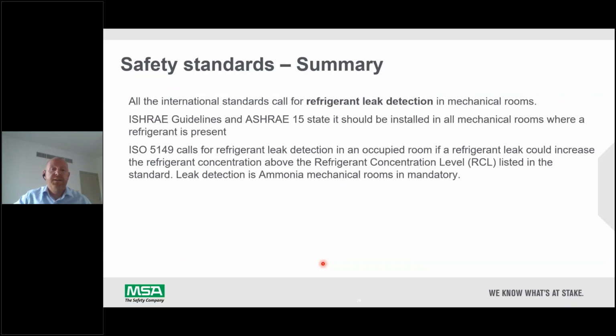So, safety standards, a summary. All of the international standards actually call for leak detection in the mechanical rooms at least. ISHRAE and ASHRAE say it needs to be installed in the mechanical rooms where refrigerant is present. And then ISO 5149 calls for leak detection in an occupied room if there's a risk of the leak going above the refrigerant concentration level, which is in the document ISO 5149.